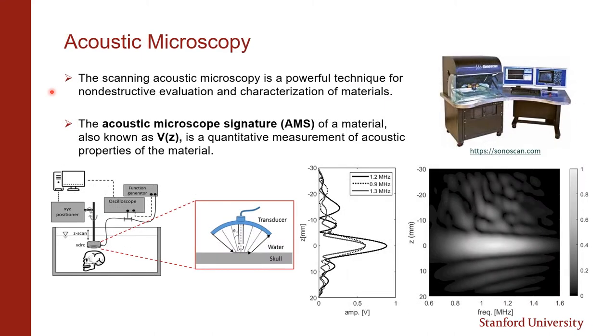The scanning acoustic microscopy is known as a powerful technique for non-destructive evaluation and characterization of materials. The proposed technology utilizes a large aperture focus transducer that is scanned towards the sample and received signals at the transducer are processed to generate a response curve of the sample, which is also called a V(z). This is a unique pattern of the scanning spot and contains a wealth of information about the properties of the substrate material. This response curve is further analyzed to extract the material properties of the samples.